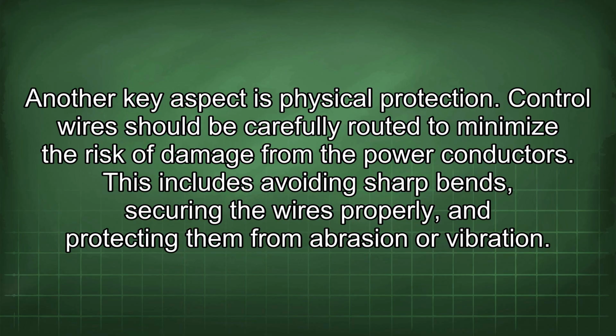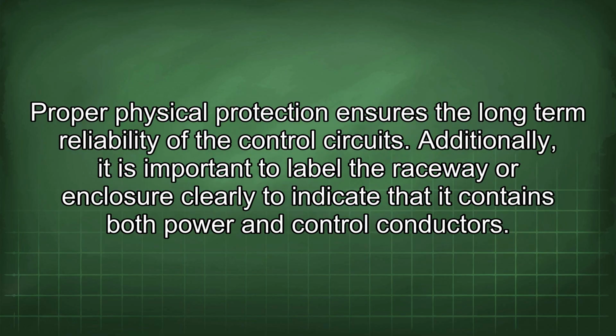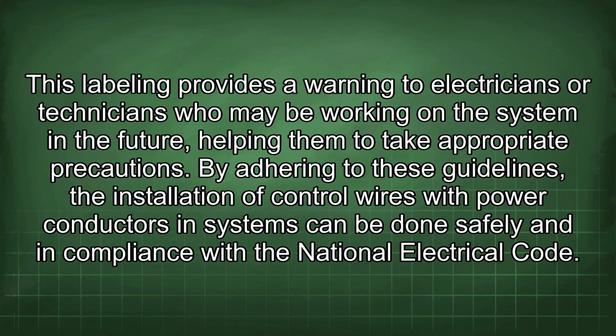Another key aspect is physical protection. Control wires should be carefully routed to minimize the risk of damage from the power conductors. This includes avoiding sharp bends, securing the wires properly, and protecting them from abrasion or vibration. Proper physical protection ensures the long-term reliability of the control circuits. Additionally, it is important to label the raceway or enclosure clearly to indicate that it contains both power and control conductors. This labeling provides a warning to electricians or technicians who may be working on the system in the future, helping them to take appropriate precautions.